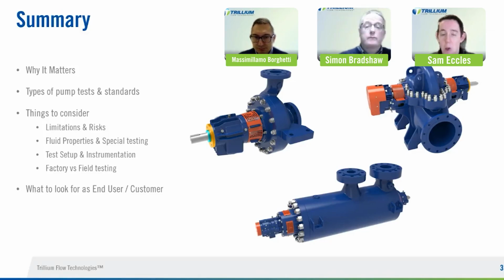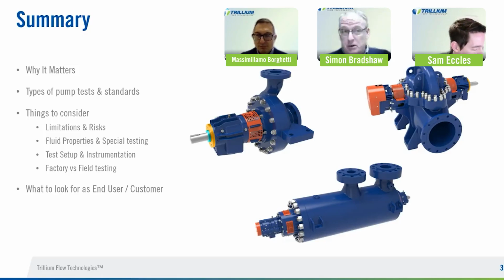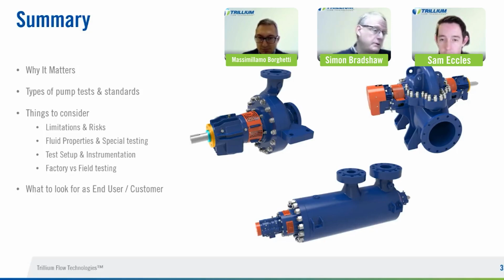We've got one from Abhinesh which Simon, if you're okay to cover. Do all pumps offered by Trillium come with performance testing as default, or does it need to be specified? If you're buying an API 610 pump, certain testing is mandated in that standard. So your performance test has to happen. Other tests beyond that, you have to specify. They're optional tests, for example an NPSH test or a mechanical run test. You need to call those out on the data sheet.